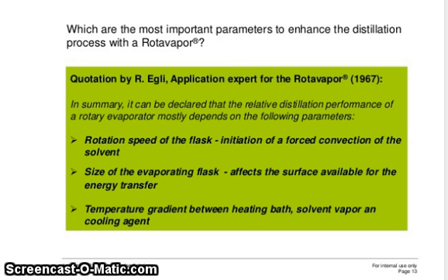Which are the most important parameters to enhance the distillation process with a rotary evaporator? According to our application expert: the relative distillation performance mostly depends on rotation speed of the flask, initiation of forced convection of the solvent, size of the evaporating flask (which affects the surface available for energy transfer), and the temperature gradient between the heating bath, solvent vapor, and cooling agent.